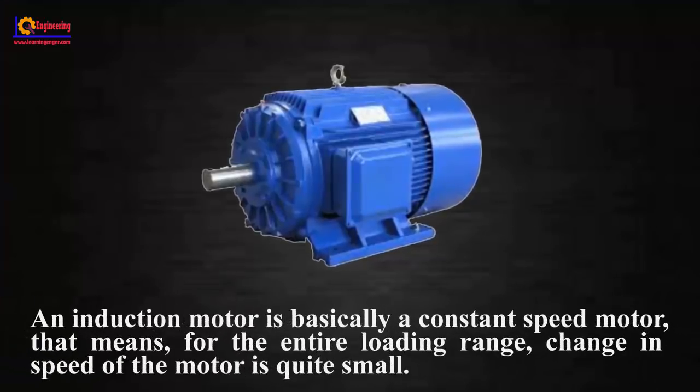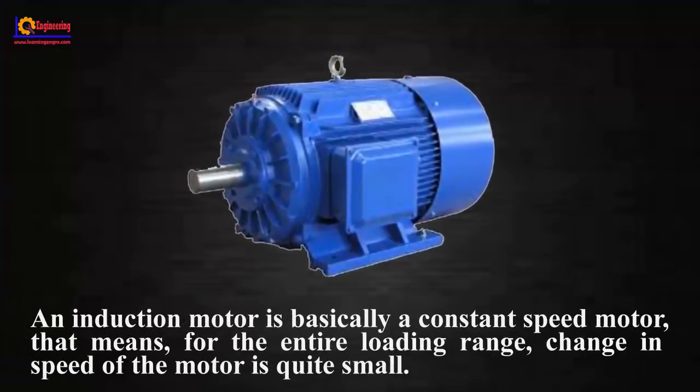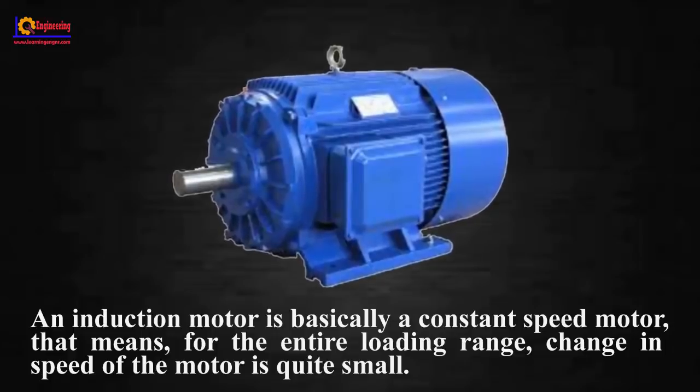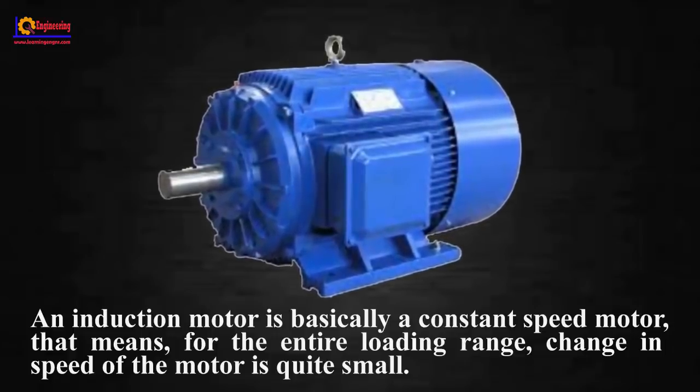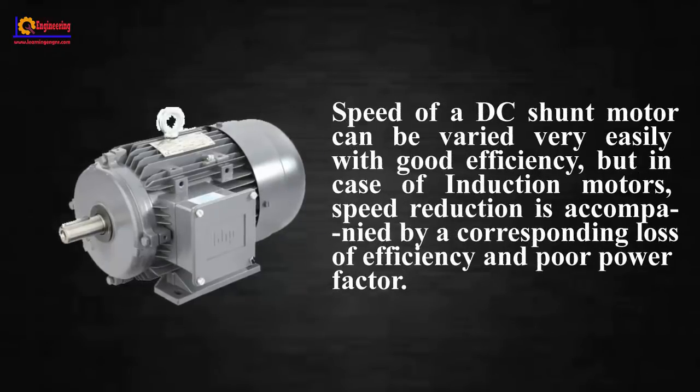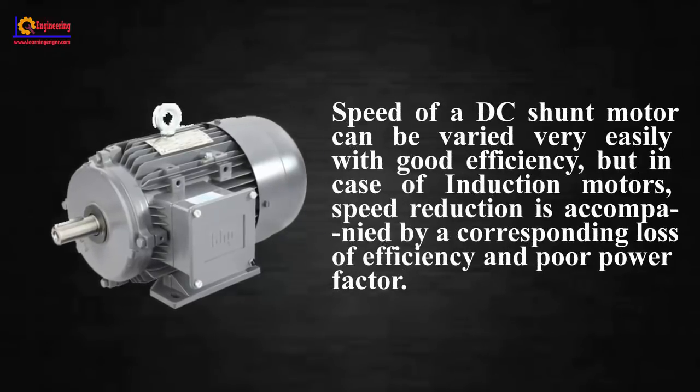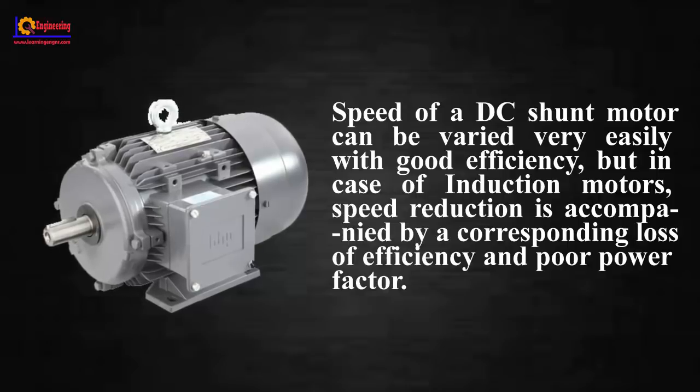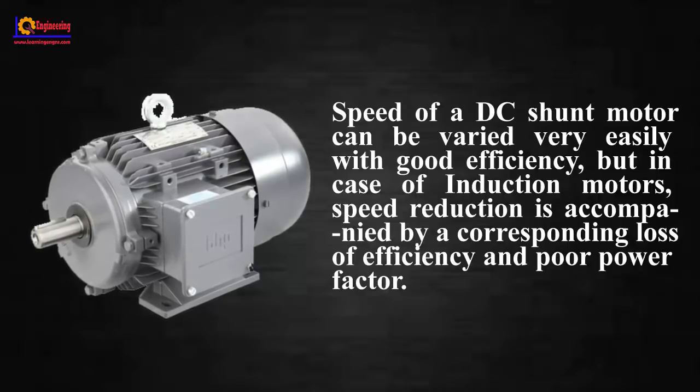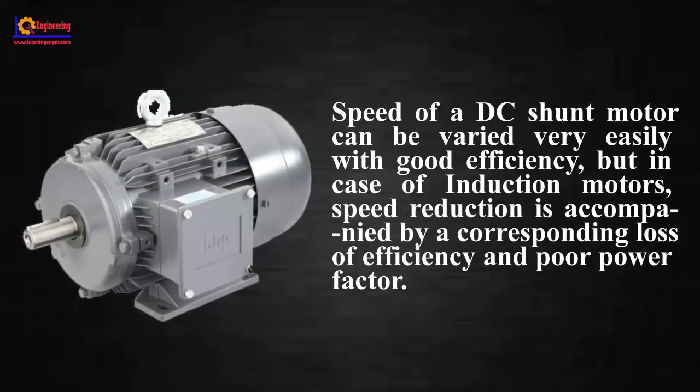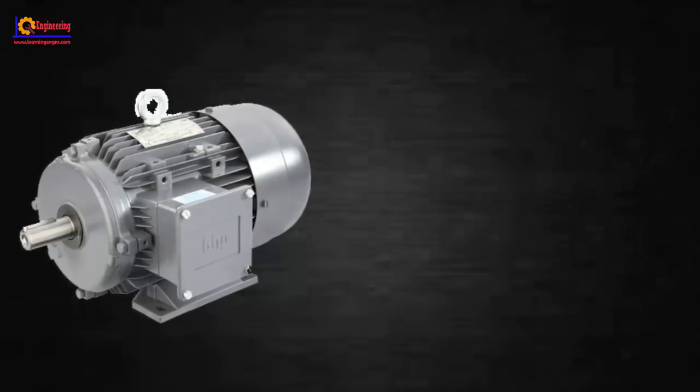An induction motor is basically a constant speed motor. That means for the entire loading range, change in speed of the motor is quite small. Speed of a DC shunt motor can be varied very easily with good efficiency, but in case of induction motors, speed reduction is accompanied by a corresponding loss of efficiency and poor power factor.